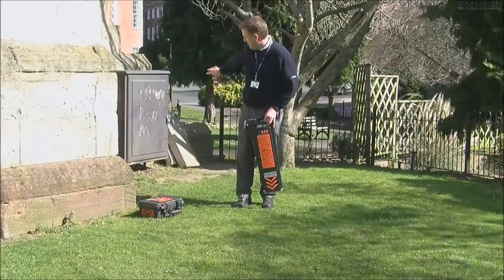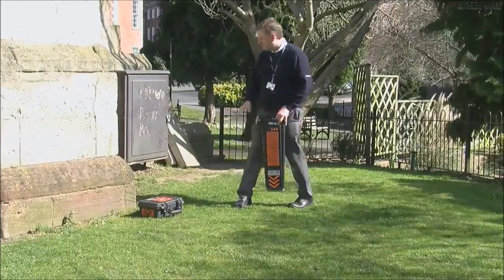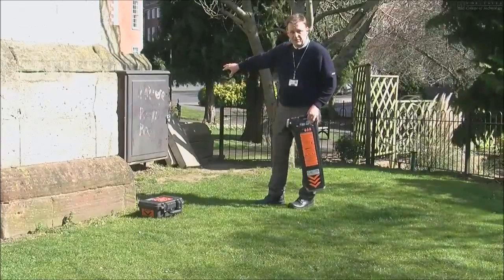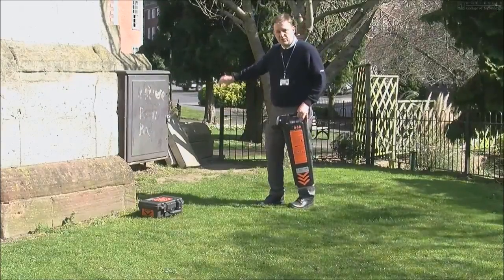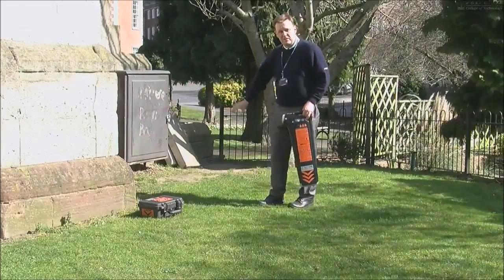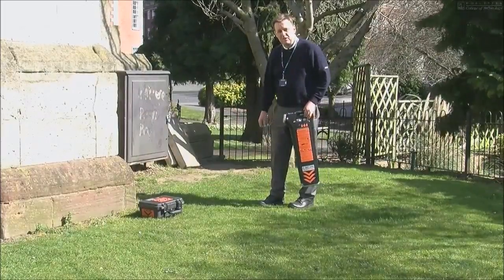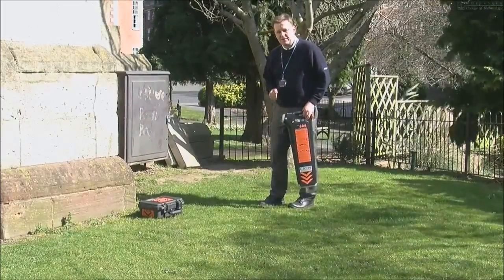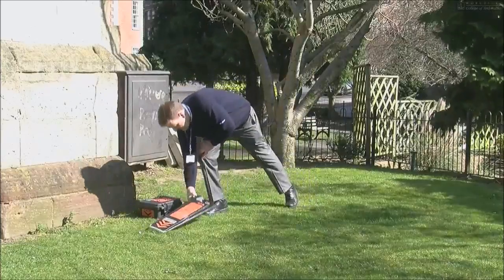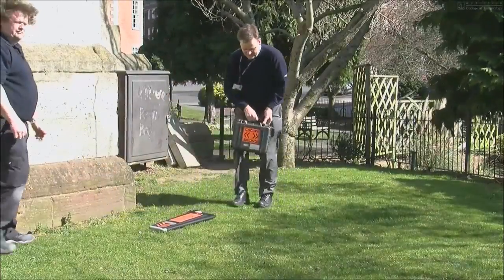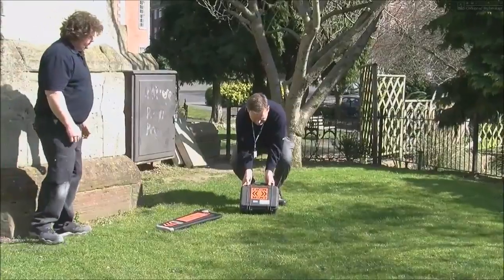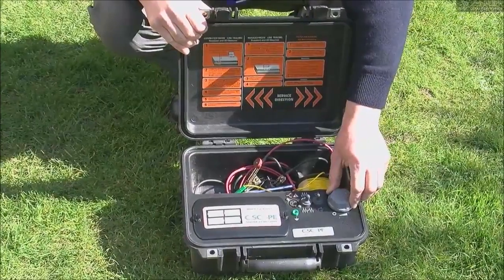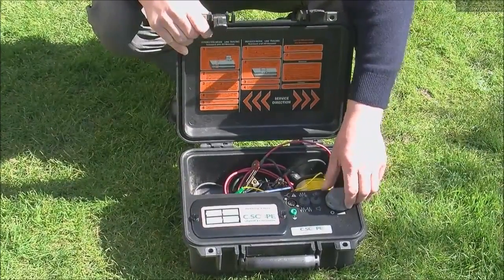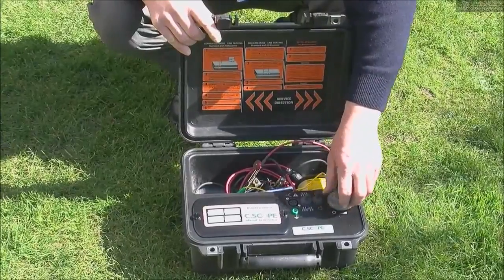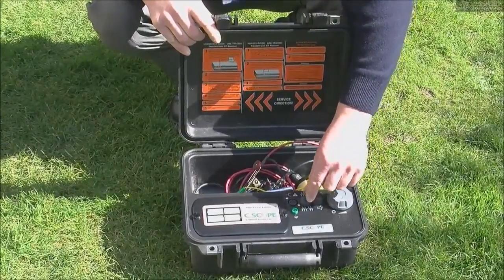and we're going to set the Genny up at the street furniture where the actual fuse board is. This will send a signal into the ground. We'll then trace the signal along the ground to the lamppost and identify where the cable is buried in the ground. So this is the signal generator. We simply switch the signal generator on, turn the volume up, makes a beeping noise.